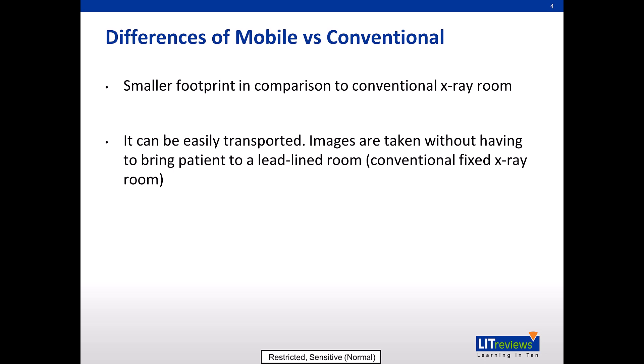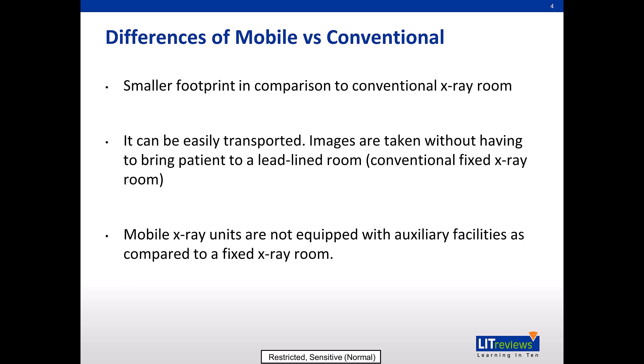There are differences between mobile and conventional x-ray units. Essentially, a mobile x-ray unit is smaller than a conventional fixed unit and can be moved. It allows radiographers to take x-ray images of patients without having to transport them into a specially lead-lined room. Mobile x-ray units are not equipped with auxiliary facilities, which includes the degree of flexibility and movement of the x-ray tube, table, and the availability of positioning aids. As such, it has limitations in performing certain bedside imaging.